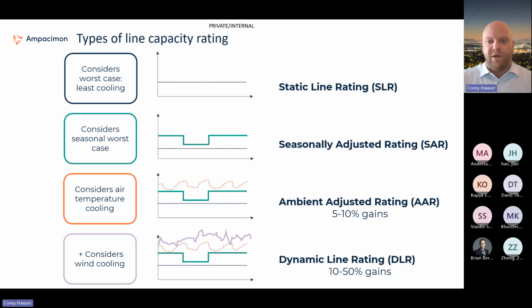And the last one is our dynamic line rating. This is when we truly bring in an accurate wind measurement that is occurring in real time, in our case measured by a sensor sitting on the conductor. As you can see, with the ambient adjusted ratings you're looking at a roughly 5 to 10% gain on average. With DLR, it could be anywhere from 10 to 50%. And the biggest thing here is that this value is going to be accurate because it's taken directly from the line. So you don't have to worry about damage to your infrastructure or safety or damage to anything below the conductor, because you're getting an accurate reading from that point. So you're getting to harness all these extra gains without the worry, so to say.